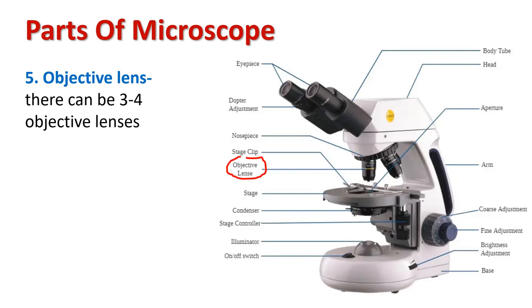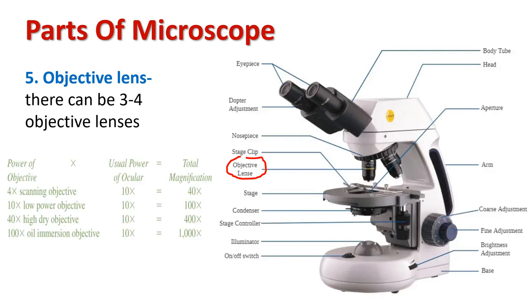There can be three or four objective lenses mounted on the nosepiece. These lenses have different magnification powers that help in a thorough and deep examination of the sample. The scanning objective gives a total magnification of 40x, the low power objective gives 100x, the high dry objective gives 400x, and the oil immersion objective lens gives a total magnification of 1000x.